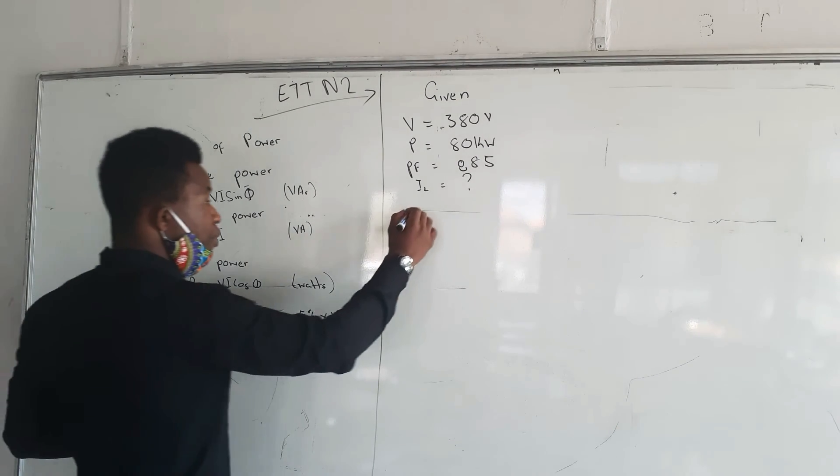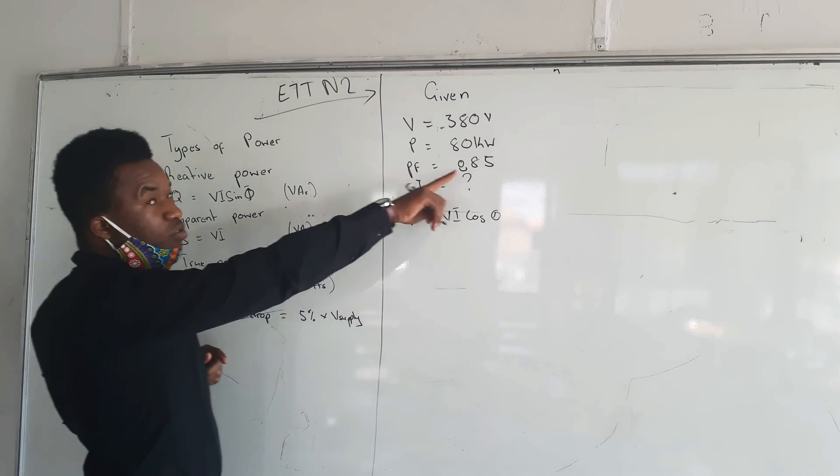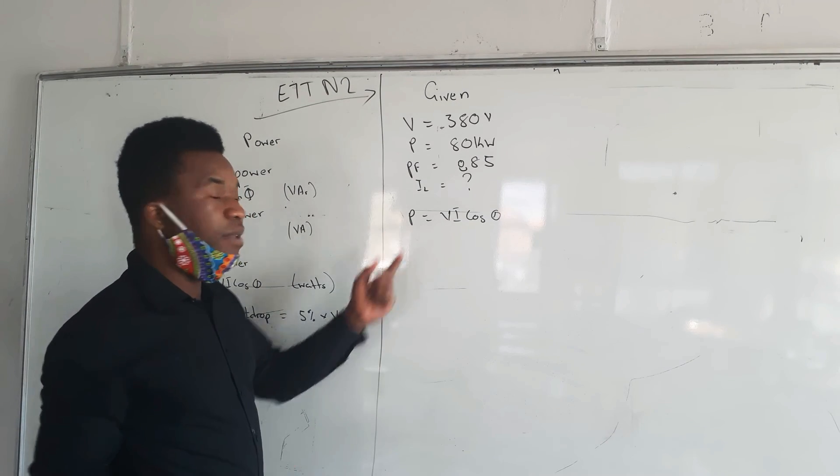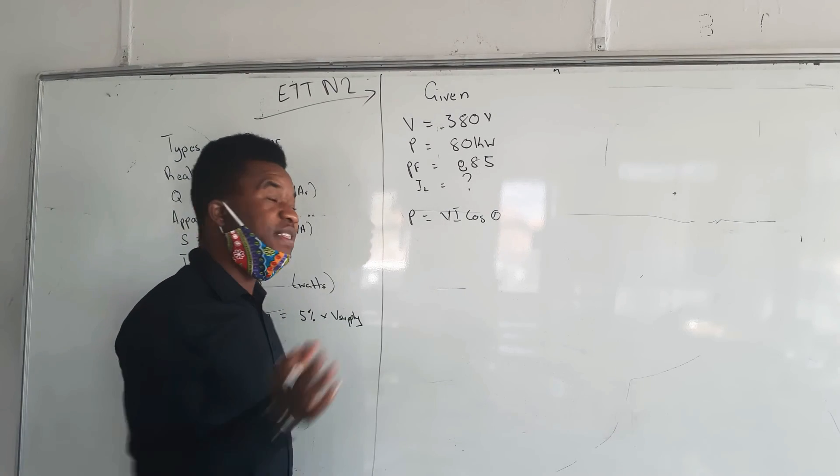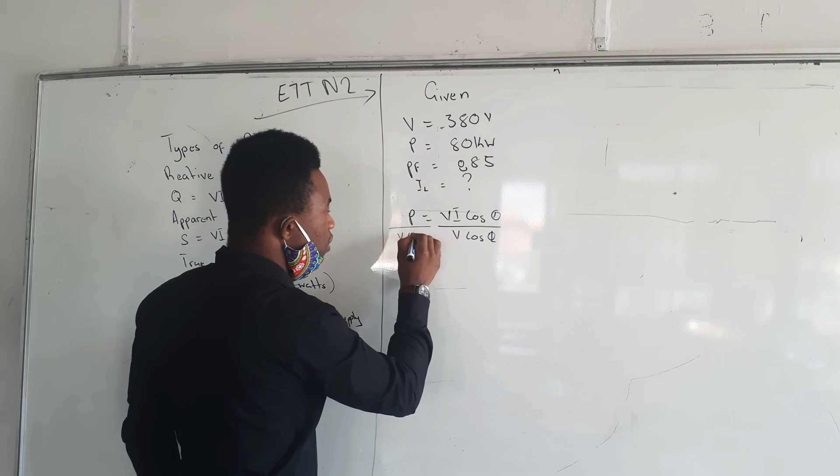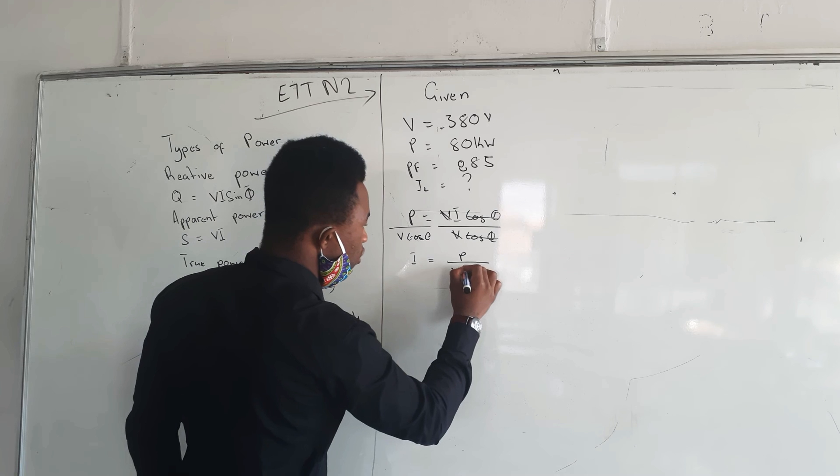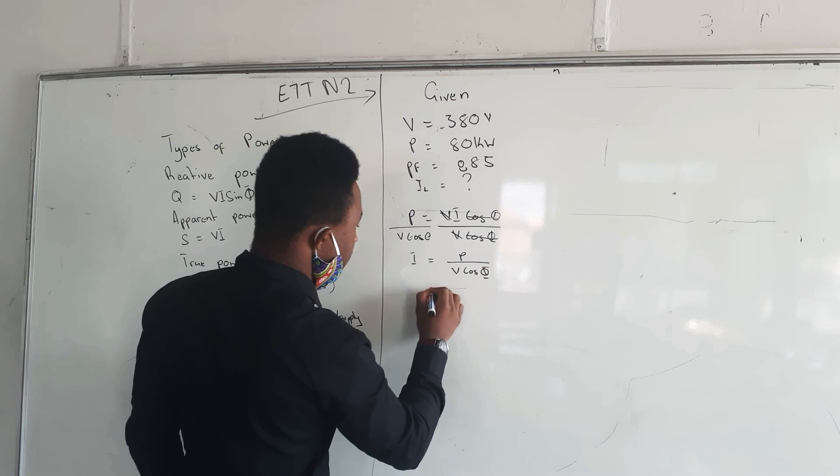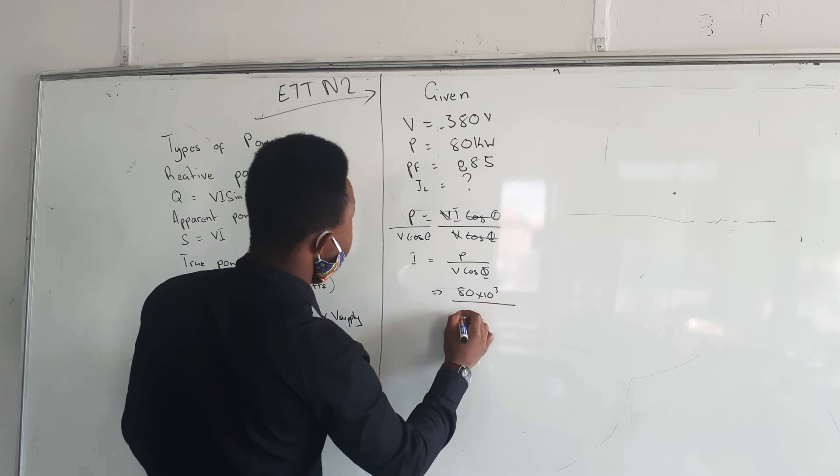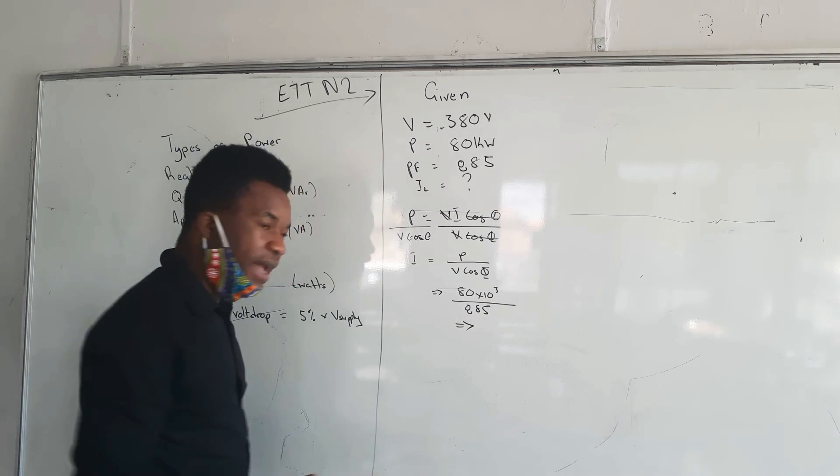The cos theta represents the power factor. I like to make I the subject of the formula first. I'm going to divide by V cos theta, and this will cancel. My current equals P over V cos theta. What is my P? It's 80 times 10 to the power 3 divided by my V, which is 380, multiplied by cos theta, which is 0.885, and then I'm going to get my current.